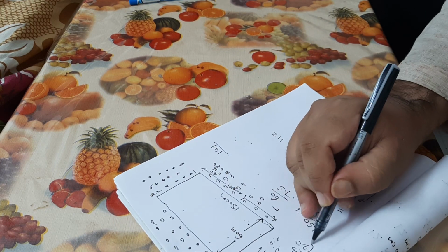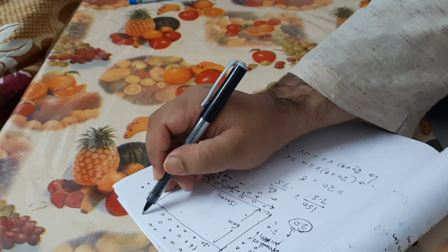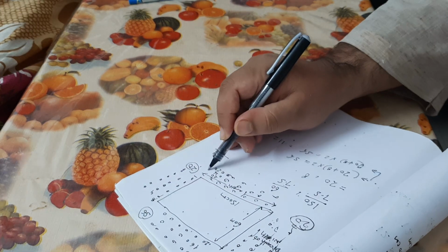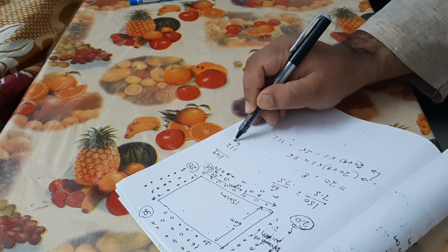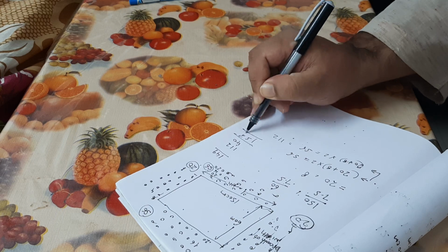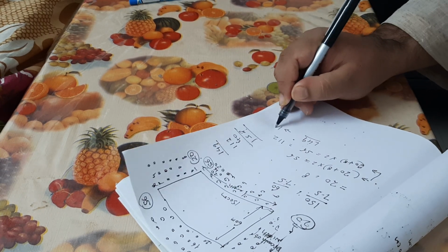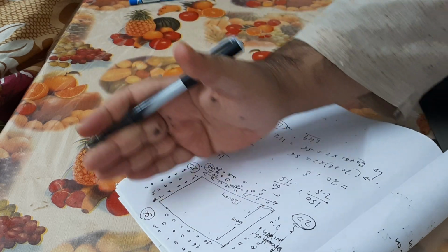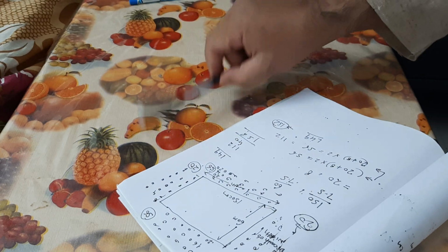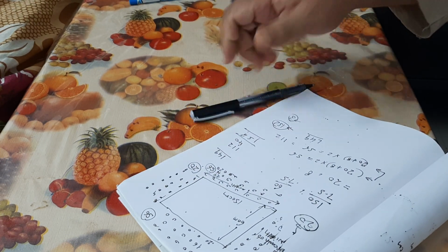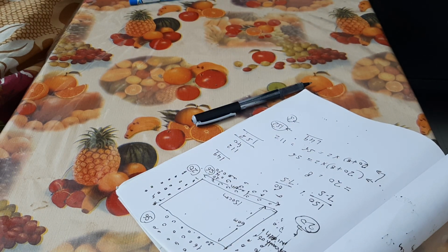So what we are seeing around the length, here 20 on one side, here 20, this happens to be 40, here 56, here 56, this is 112. So we can say 112 plus 40 happens to be 152. How much did we calculate? 149. Okay, we are getting 3 tubes more, 152, but we are keeping a radial arrangement so that the balance of heat is maintained. So okay, 3 more tubes we will incorporate for an optimum design, and this would be the best design for this transformer configuration.